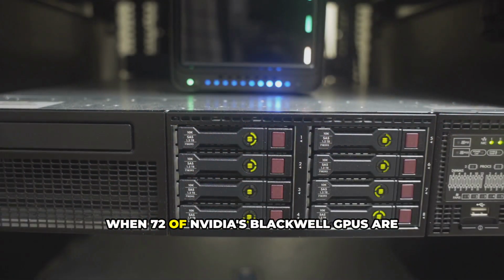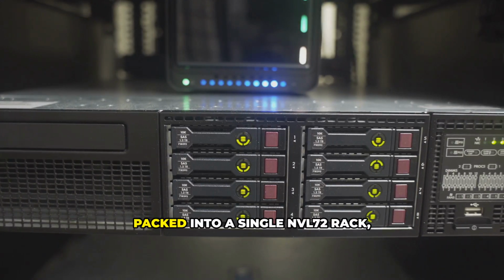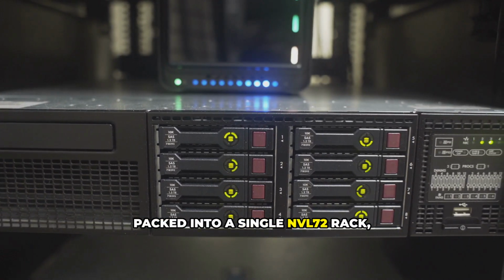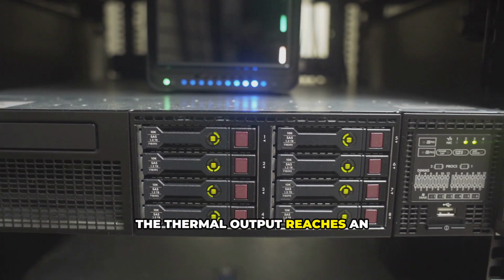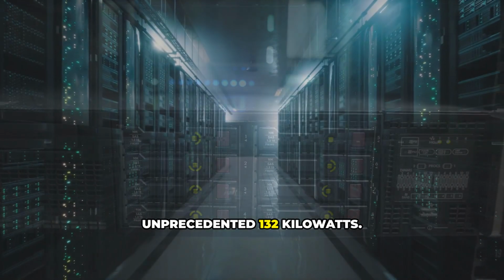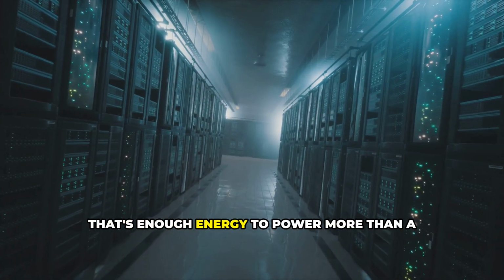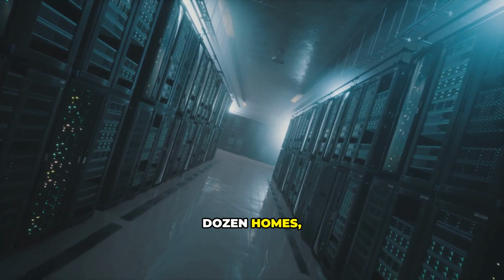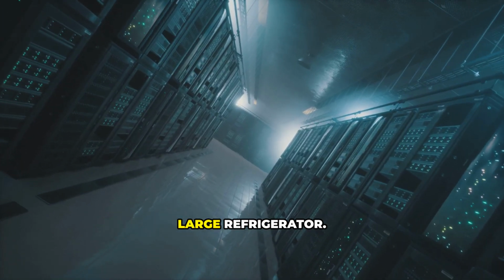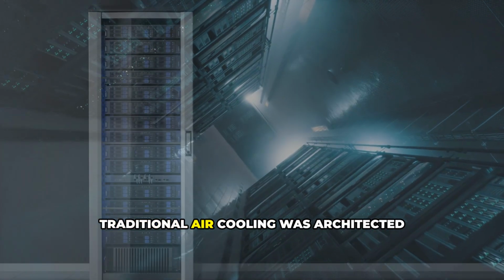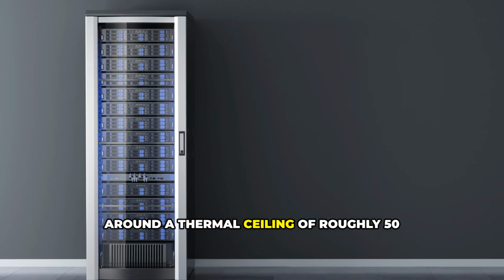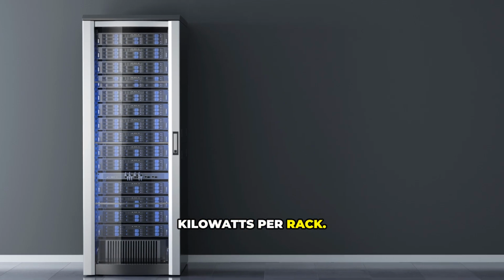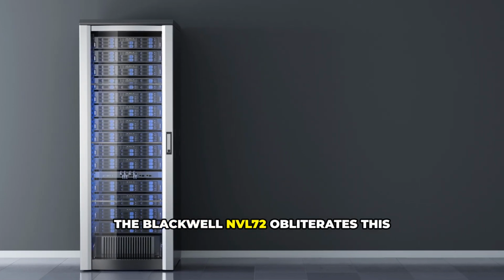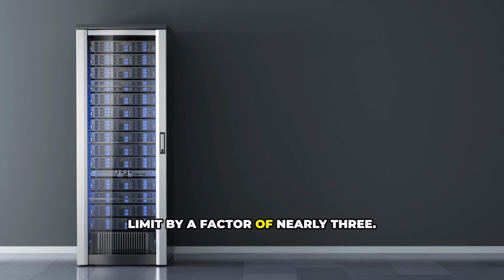When 72 of NVIDIA's Blackwell GPUs are packed into a single NVL72 rack, the thermal output reaches an unprecedented 132 kilowatts. That's enough energy to power more than a dozen homes, all concentrated into the volume of a large refrigerator. Traditional air cooling was architected around a thermal ceiling of roughly 50 kilowatts per rack. The Blackwell NVL72 obliterates this limit by a factor of nearly 3.